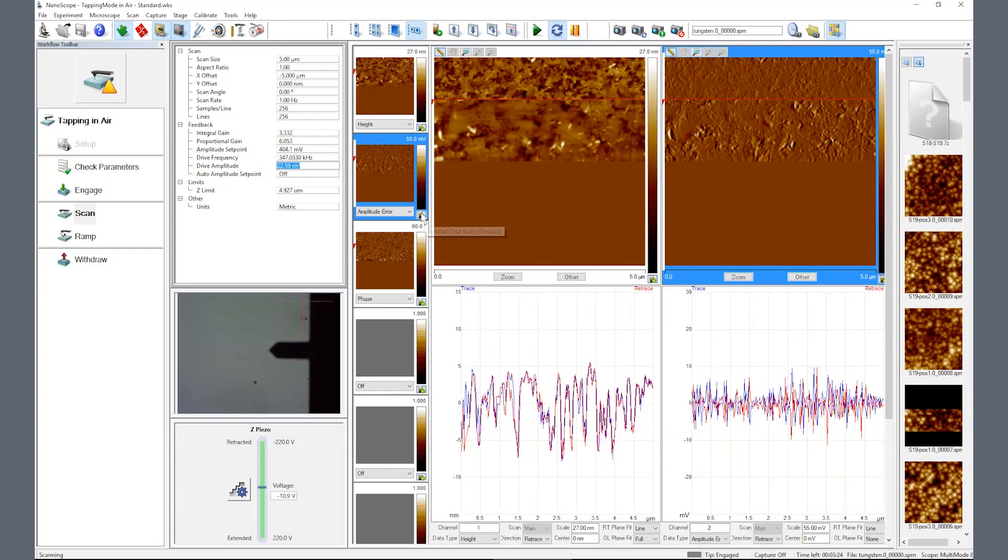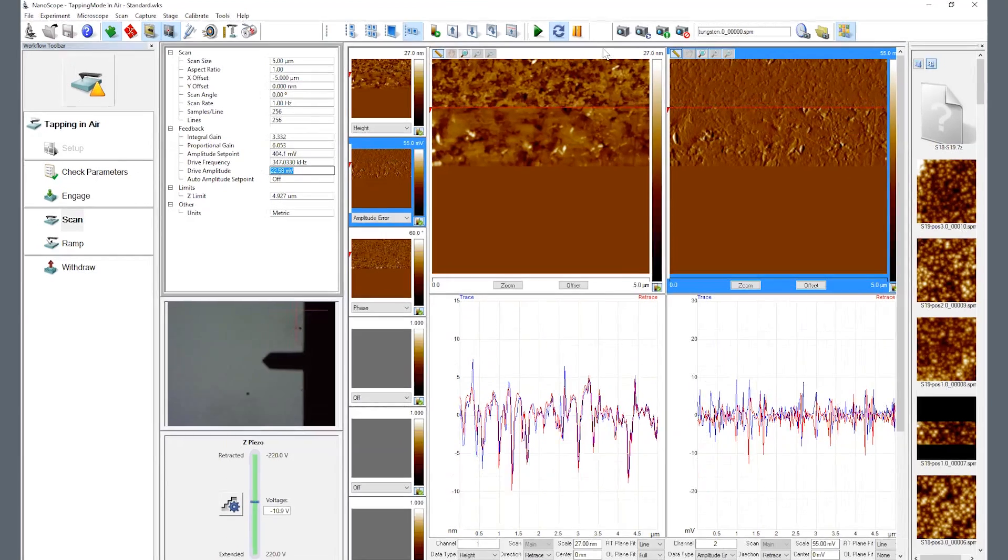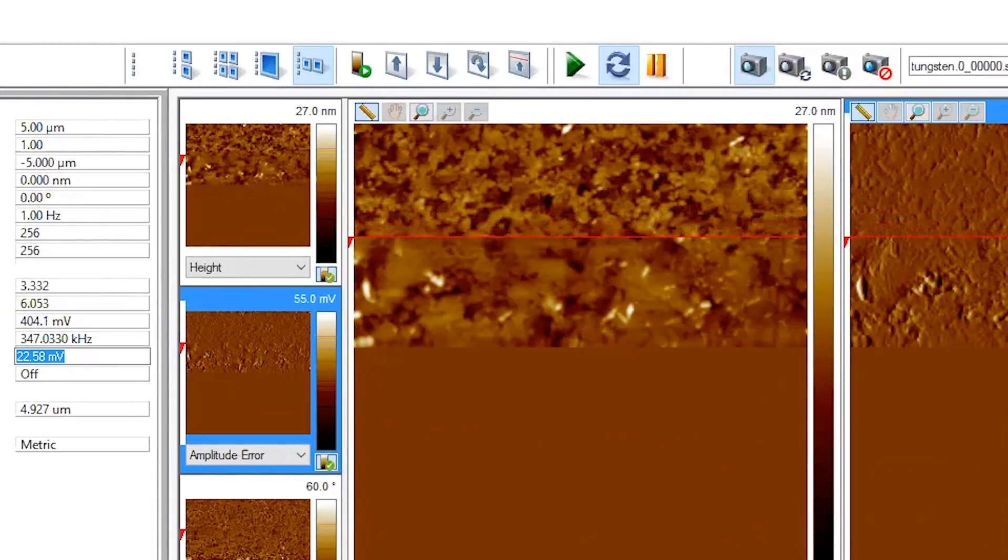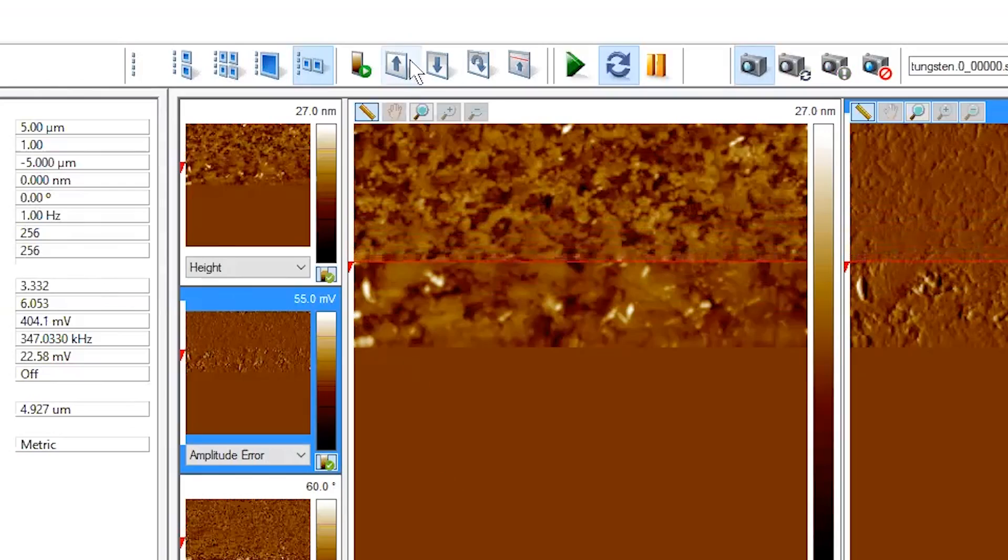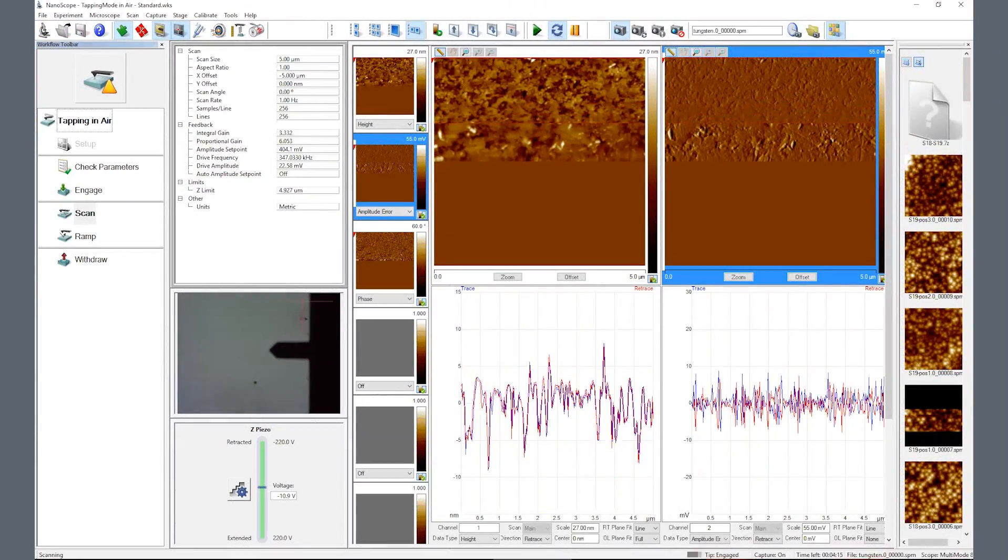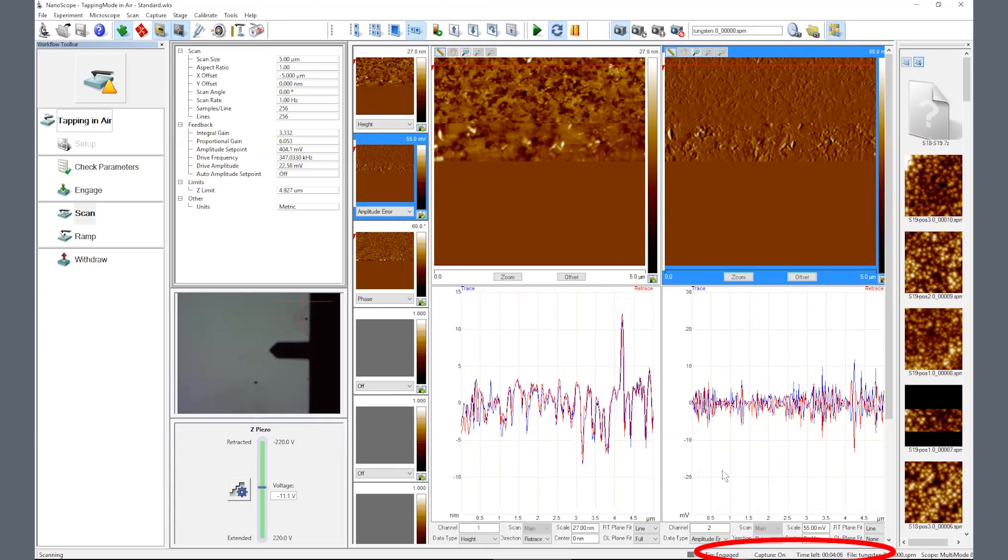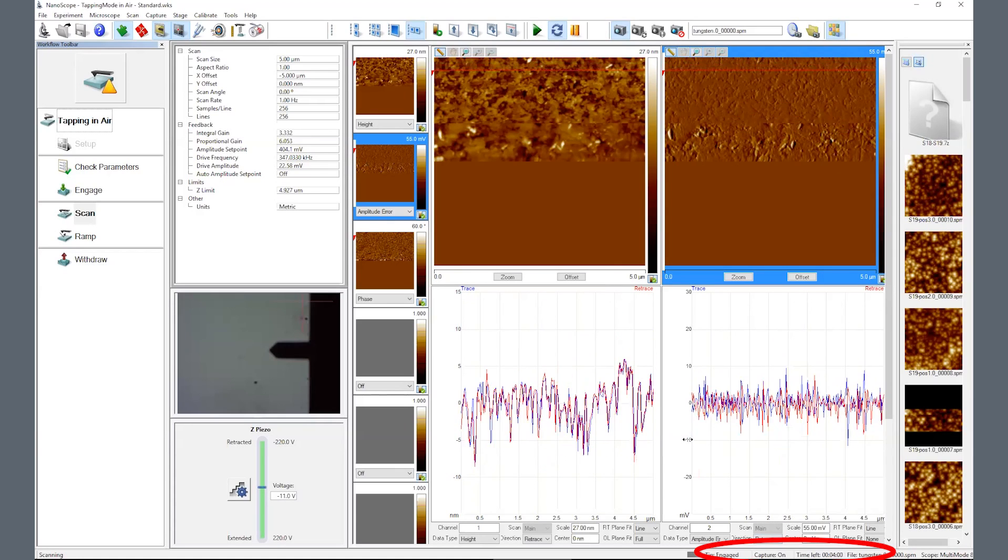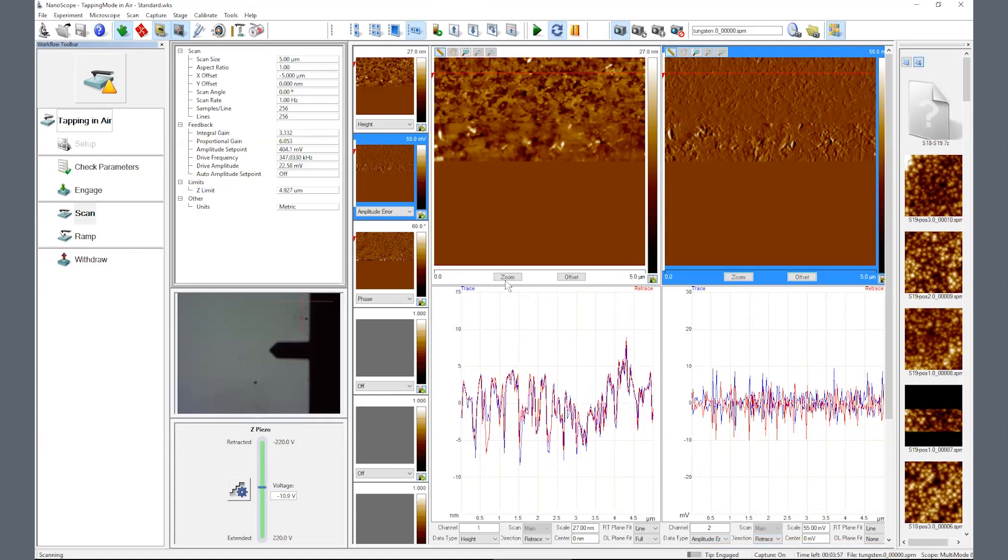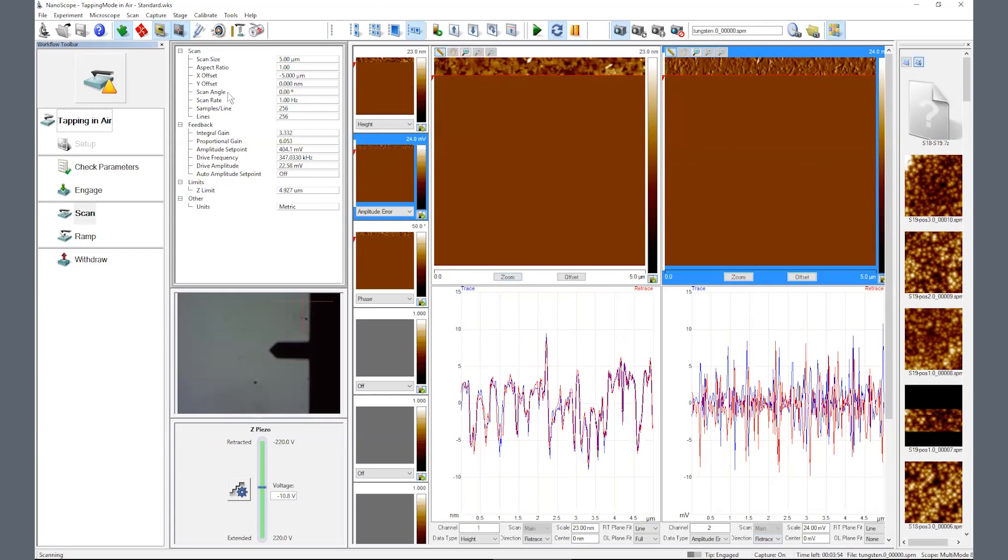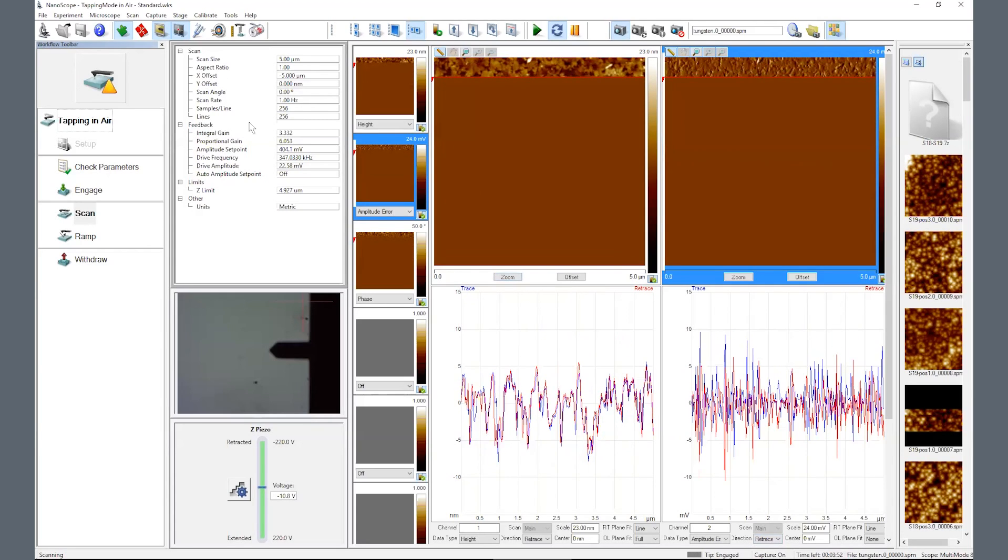Once optimized and you're ready to capture your image, select the left camera icon and begin the scan over using the frame up or frame down icon. At the lower right of the display, the capture status is displayed as on with time remaining to capture. If changes are made to any of the parameters, the capture status is displayed as next and you should use the frame up or frame down icon to begin the scan again.